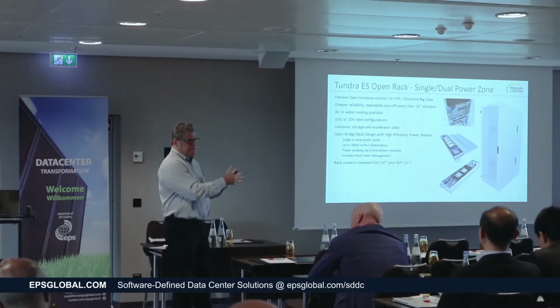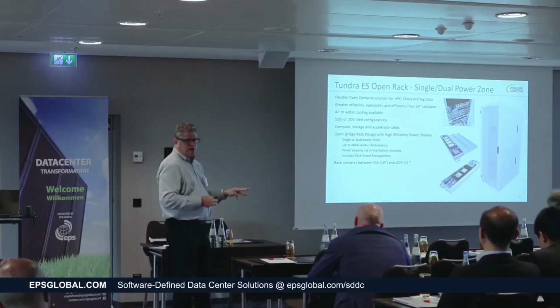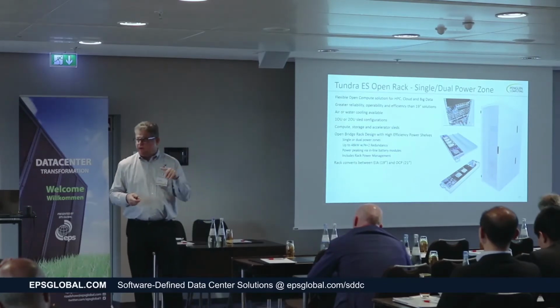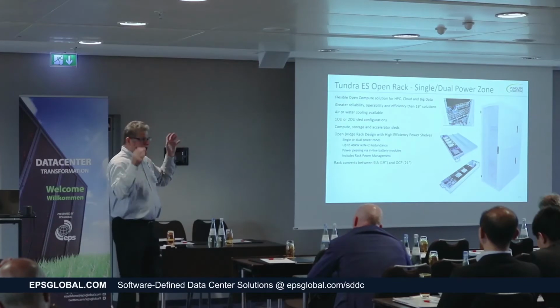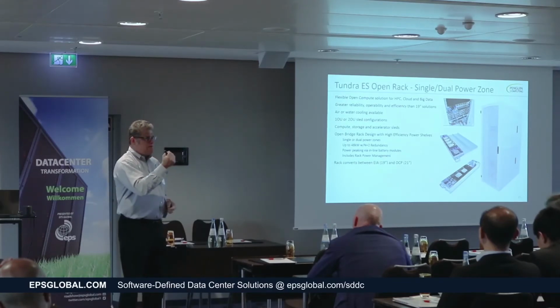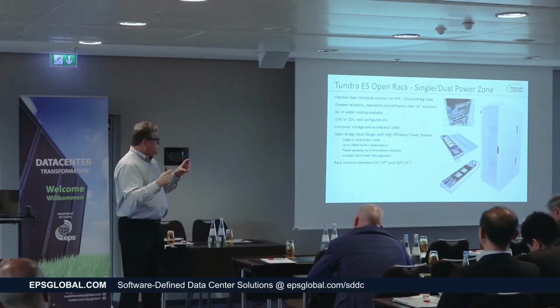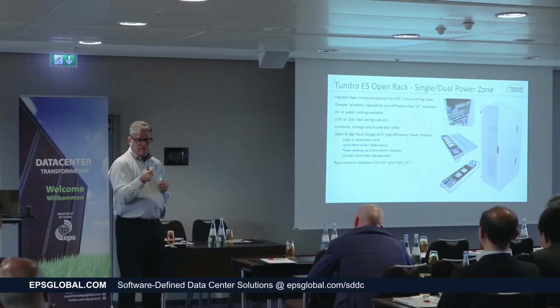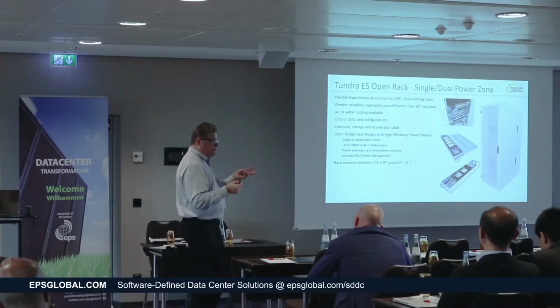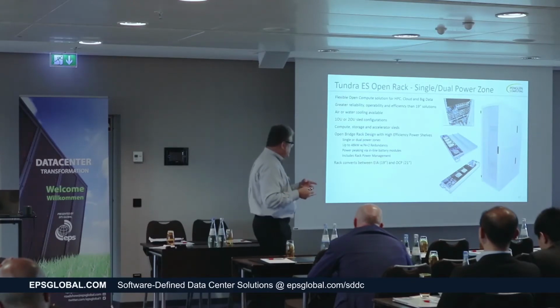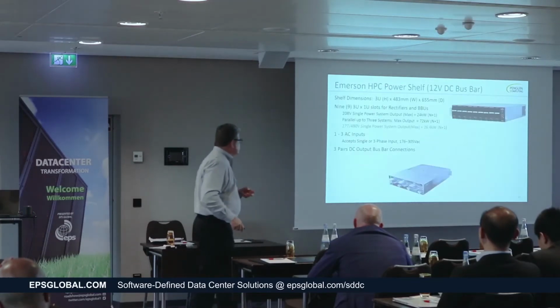We designed Tundra for version one, which has three bus bars. Version two has one bus bar. Basically what happens is we can take any type of power feed coming in, in fact I'm working with a telco customer bringing in minus 48 volts. The power shelf takes that and converts it into 12-volt power, which is what your servers run on, so it's a 12-volt bus bar, either single or triple.